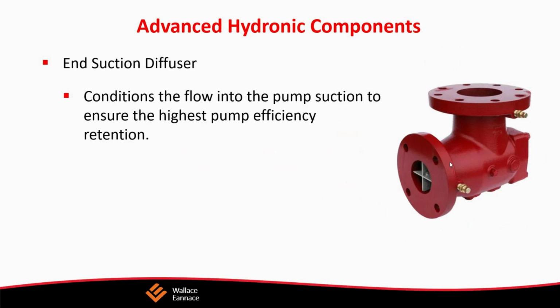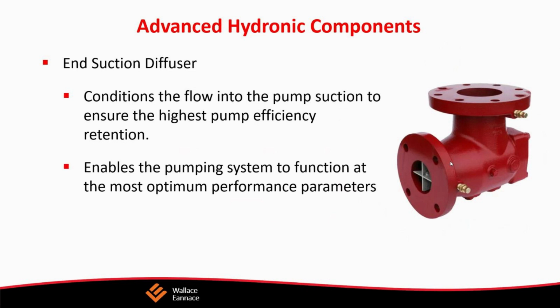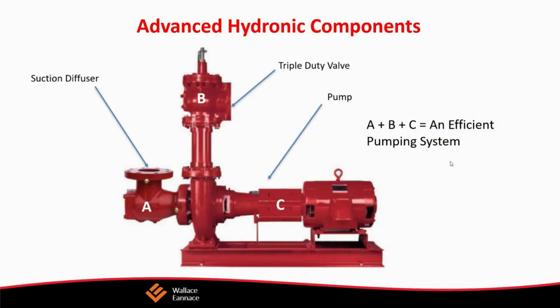One of the things we also use in systems, especially on large pumps, is a triple duty valve. Typically, they are connected to the discharge side of the pump, and they provide 3 functions in one device. They're a calibrated balancing valve, they're a spring-loaded check valve, and they're an isolation shutoff valve, hence the term triple duty valve. Triple duty valves come in a wide range of sizes. They come in a straight pattern flange from 2 to 14 inches, groove from 2 to 12 inches, and balanced straight patterns from 3 to 16 inches. We also get angled pattern flanged units from 2 to 10 inches, and smaller units like you see over here, in NPT and rotatable flanges from 1 to 2 inches.